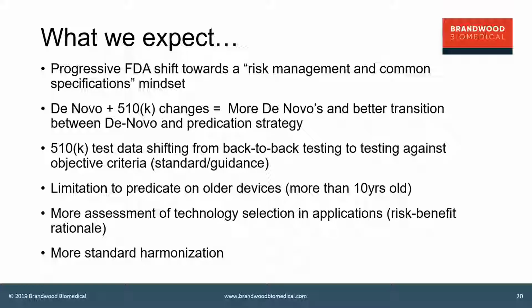We certainly believe that they are going to be limiting the scope of what can be used as a predicate device, and that they will not allow devices that are more than 10 years old to be predicates. Again, this is more on the maintenance side for them, so that they can maintain an appropriate set of devices that can be used as predicates. And they are worried that when a new device comes out, if it's only based on a predicate that's old but hasn't been used that often, or hasn't been in the marketplace for a while, there may not be the current safety and effectiveness data that they need. And sorry, I just want to add something on this.